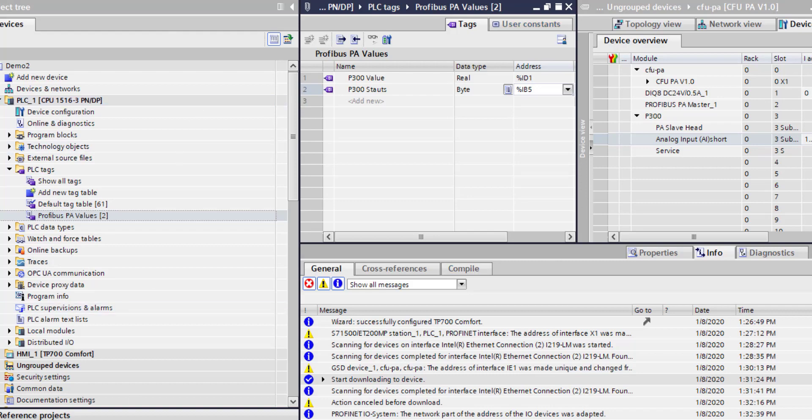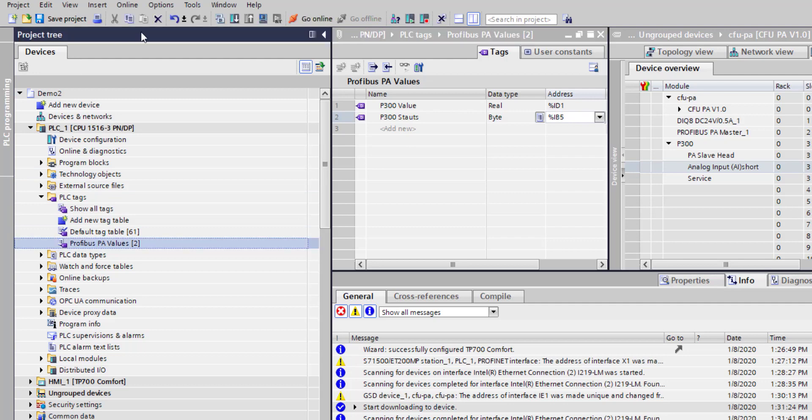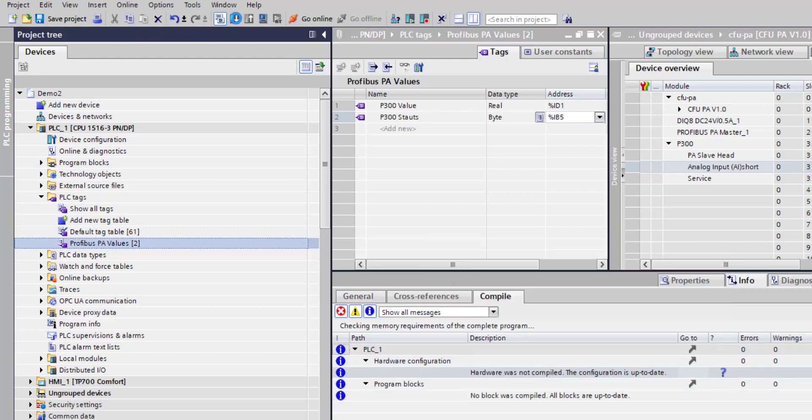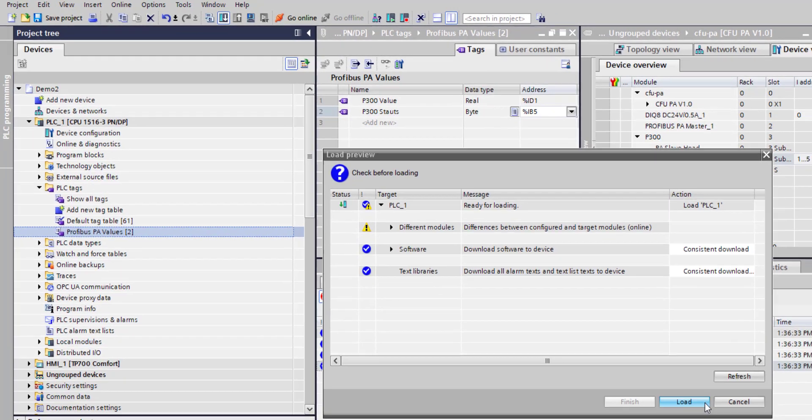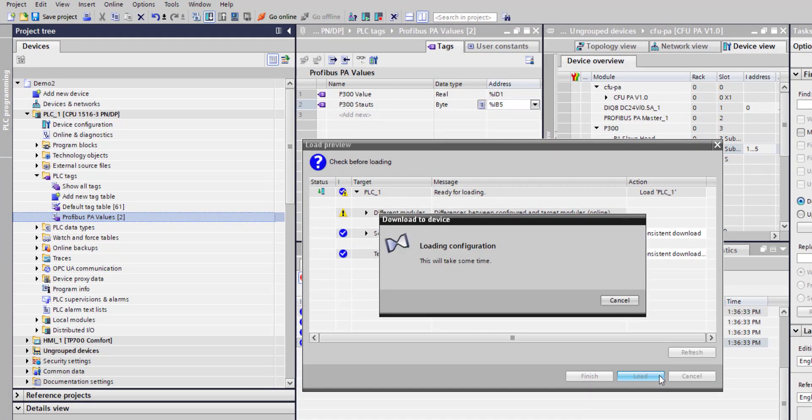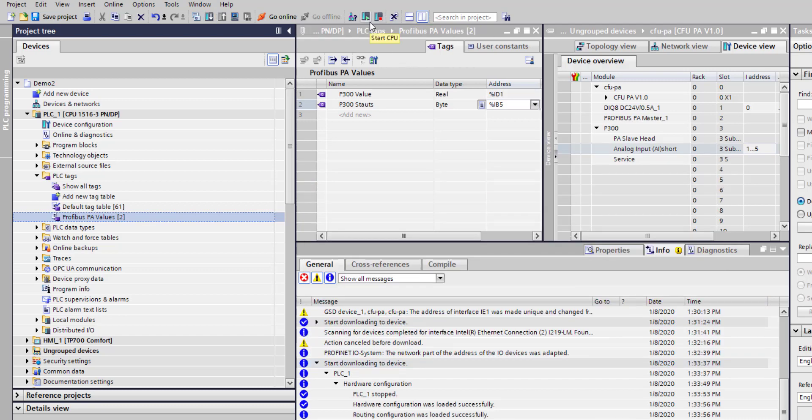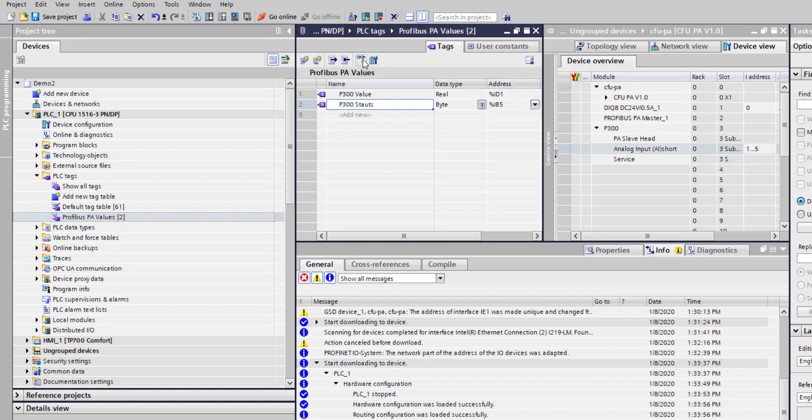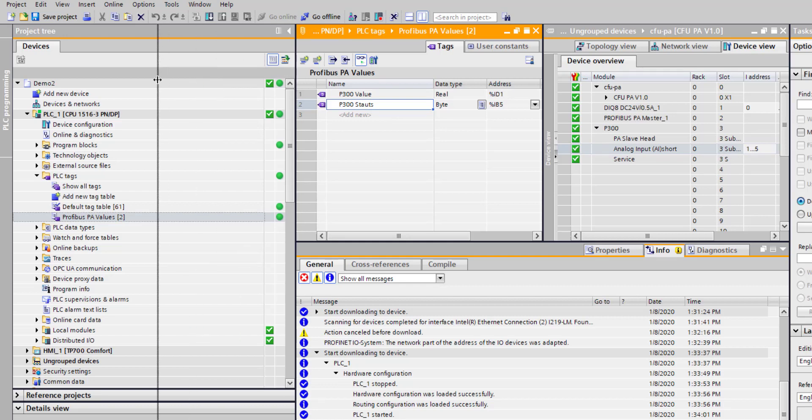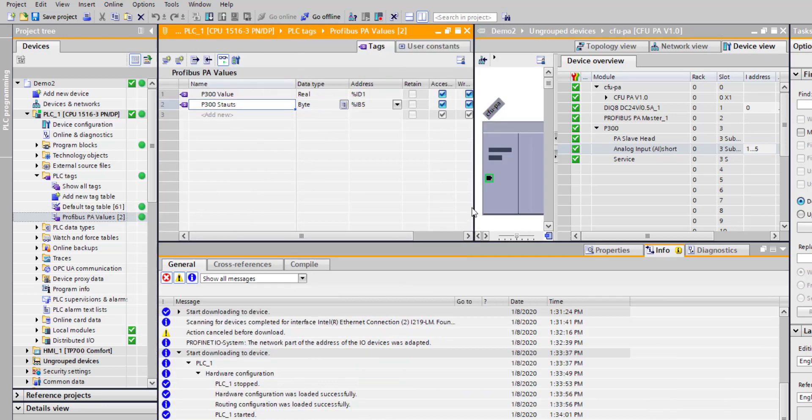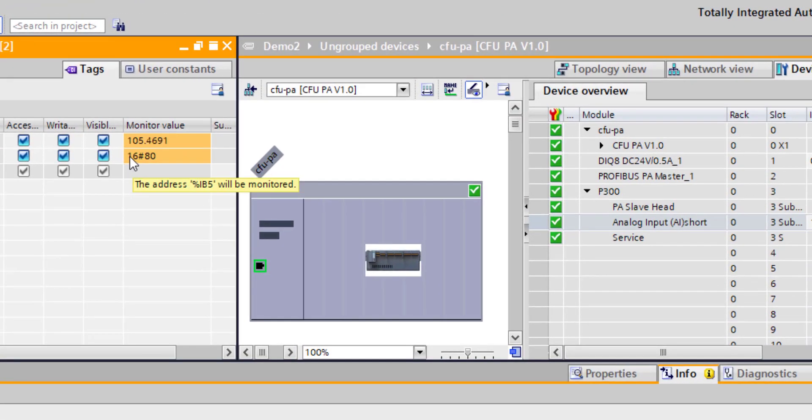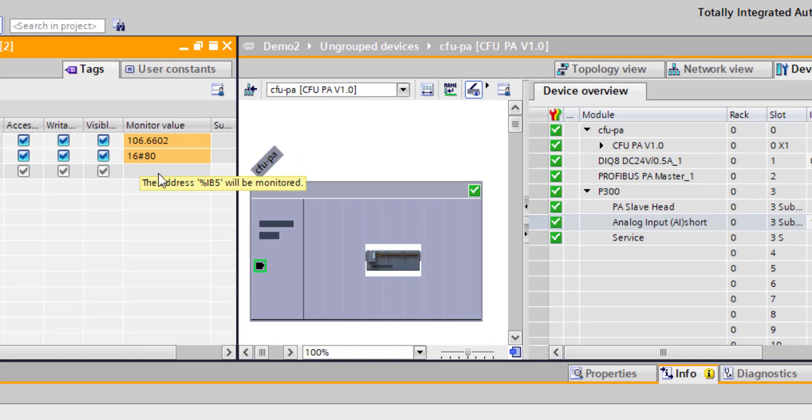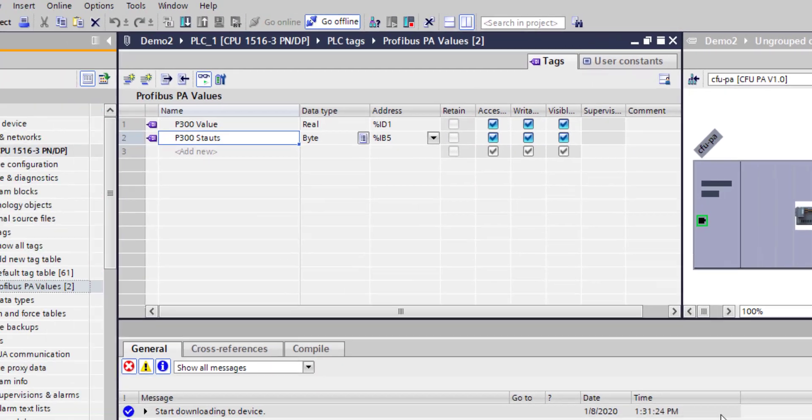I just have to compile and download that. If I put this screen into run, I can see those values are good. I can see my process values. My status byte hex 80 is healthy. If I just push down on this pressure transmitter, I can see there the update - the date time is there. There's nothing wrong with those, everything is coming back into my PLC. To get that into my HMI, don't forget to go offline.